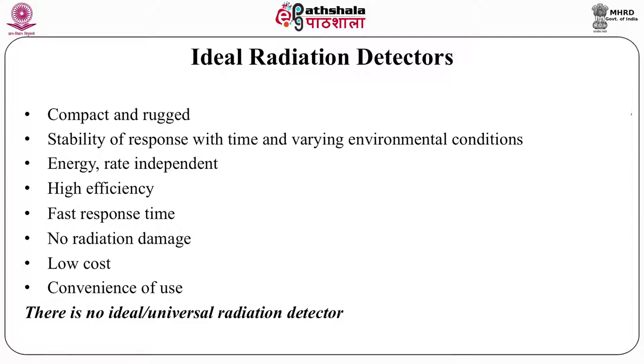The dose shown should be independent of the energy of the radiation. Similarly, its integral response should be independent of the dose rate. This ideal radiation detector should have high efficiency, fast response time, and should not itself suffer radiation damage, because over time the response of the detector would change. It should be low cost and convenient to use. But the bottom line is: there is no ideal universal radiation detector.